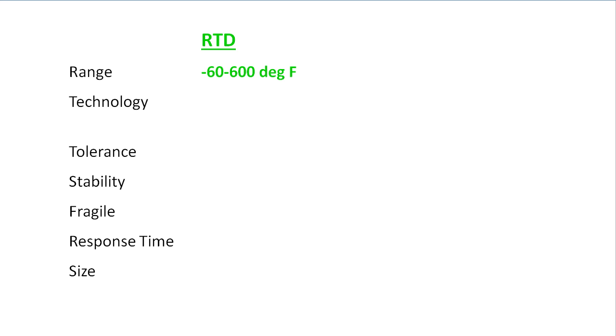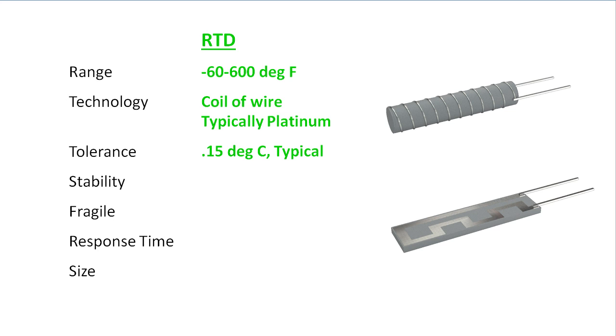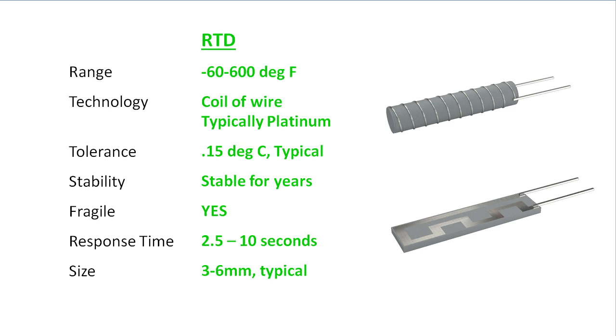Because RTDs are typically made from a very fine wire wrapped around a ceramic core or created using thin film technology, they provide accurate, repeatable results over the long term. But they are also fragile, they have a long response time, and are bigger than thermocouples.